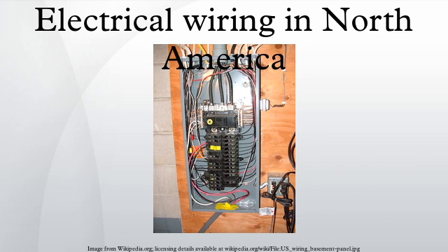Furnaces, water heaters, heat pumps, central air conditioning units, and stoves must be on dedicated circuits. The code provides rules for sizing electrical boxes for the number of wires and wiring devices in the box. In a fixture, the brass screw is hot, and the silver screw is neutral. The grounding screw is usually painted green. The foregoing is just a brief overview and must not be used as a substitute for the actual National Electrical Code.